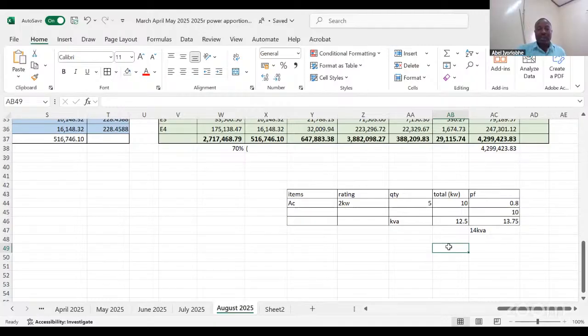So this is how you use power factor to determine the size of your cable or generator. When you already know what is installed correctly in your facility, you aggregate the equipment ratings in kilowatts. You have to divide it by 0.8 to get your real kVA. This is the real power, this is apparent power.